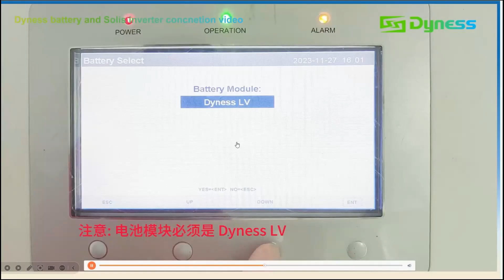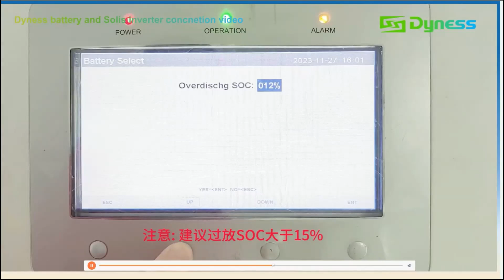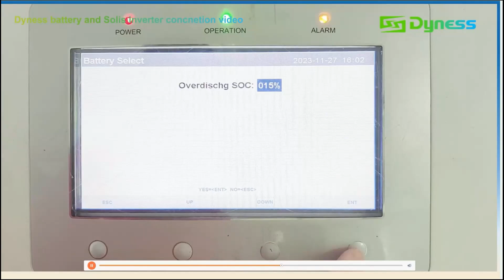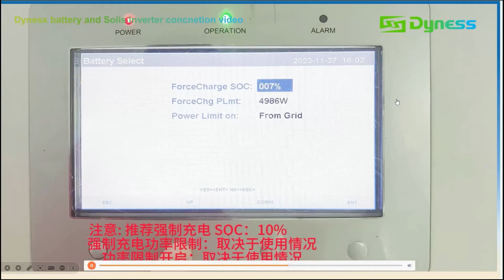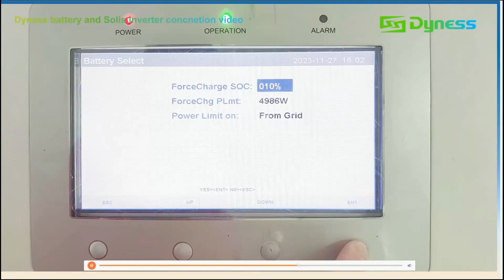And you can select the battery in storage side and choose Dyness LV. And choose the battery. The battery type is the final process to make the battery and the inverter communication normal. And do the force charge settings, and you can set 10%. It's better to set 10% or above.